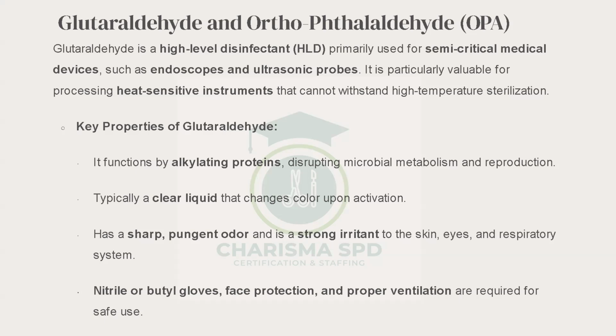It is particularly valuable for processing heat-sensitive instruments that cannot withstand high temperature sterilization. Key properties. Pause there, please. When you come to high temperature sterilization, we are talking of 270. Well, that's the dynamic. With the gravity, we are talking about 250, but that's also still high.